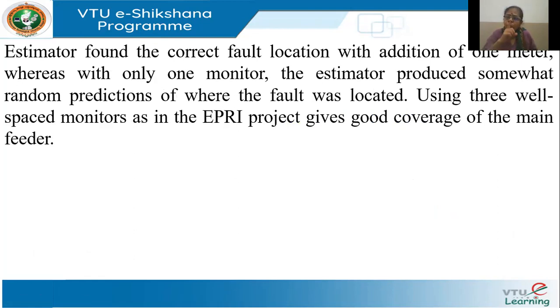With only one monitor, sometimes the model gave erratic results for the location of the fault. This is because two different locations of faults on the consumer side can have the same effect on the feeder or on the feeder substation. Are you clear? The faults on the secondary side of two different feeders can be reflected and show a similar effect on the primary side, that is, in the substation. So if I locate just one monitor in the substation, I may not be able to get selectivity and correctly make an estimate of the fault location.